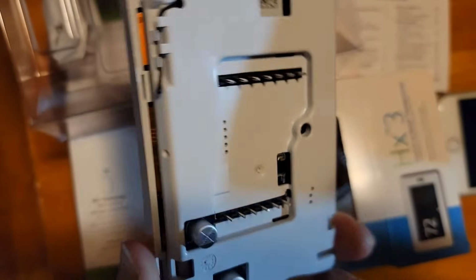The next day it was empty. Go into the indoor air handler, take the panel off, and there is oil pouring out of the coil. So ordered a new indoor coil, about $1,000, and the outdoor unit. If you want to know pricing, I'll talk about that at the end of the video for this particular piece of equipment, this HMH7. All right, there is the thermostat that we're going to install.